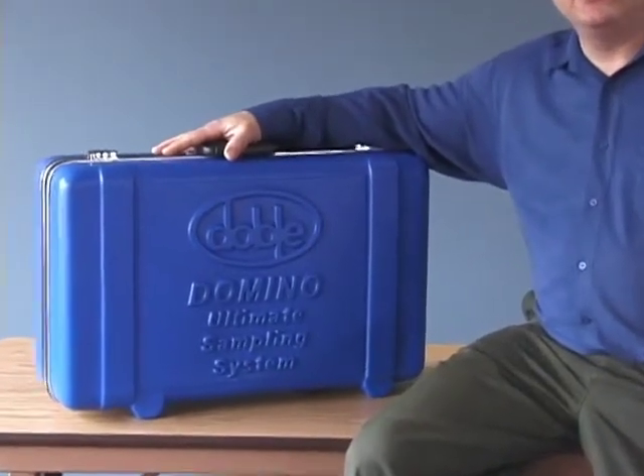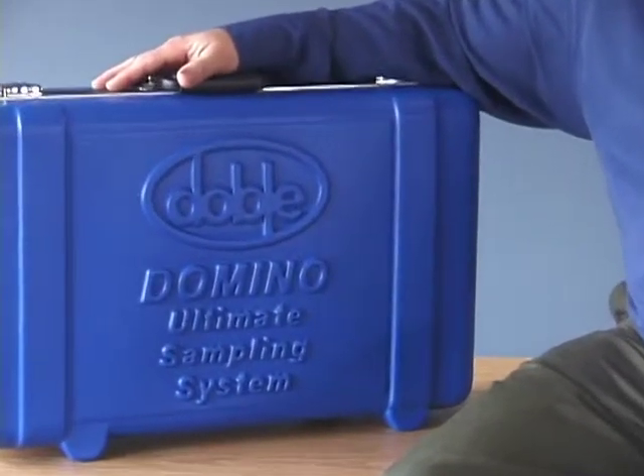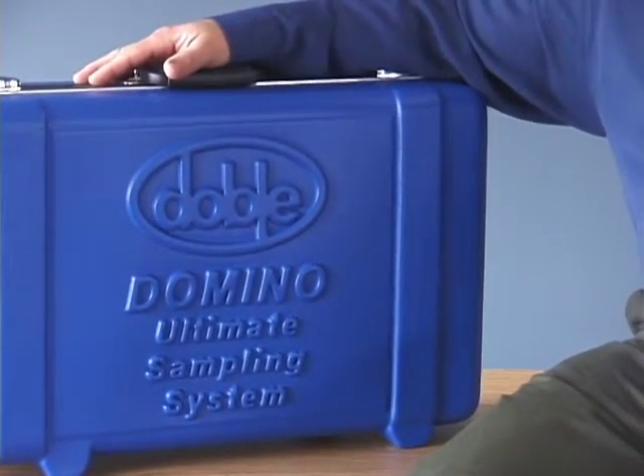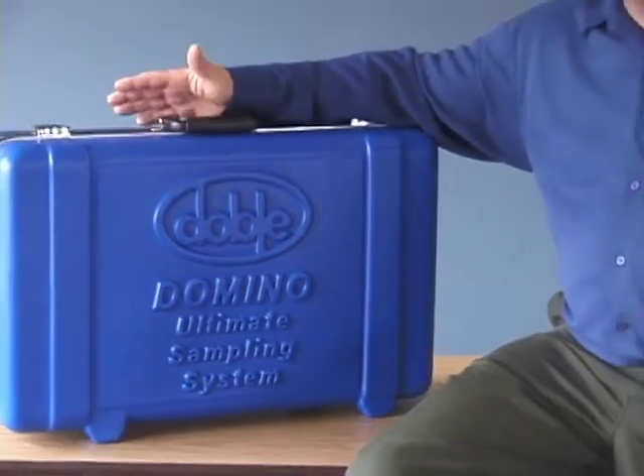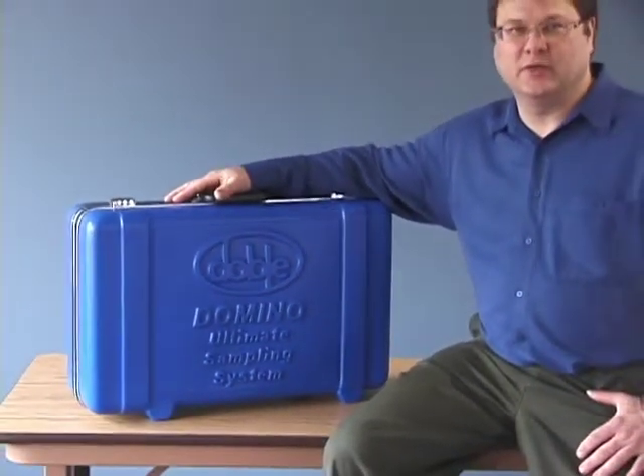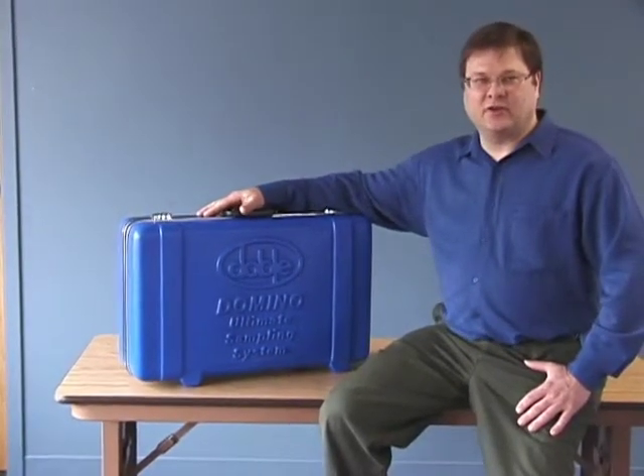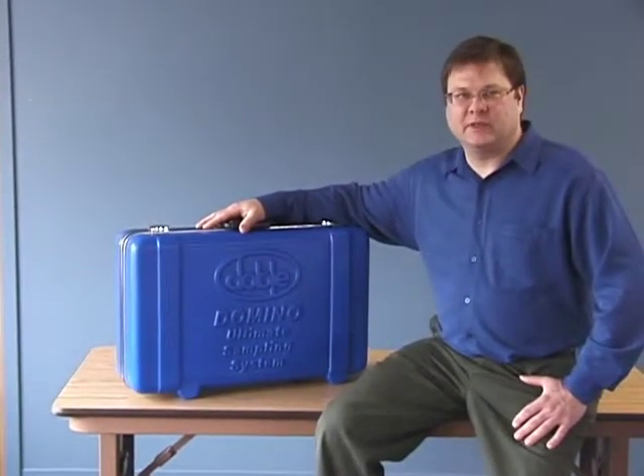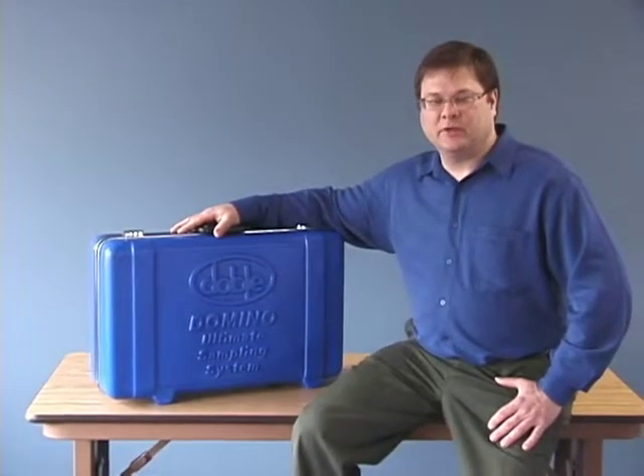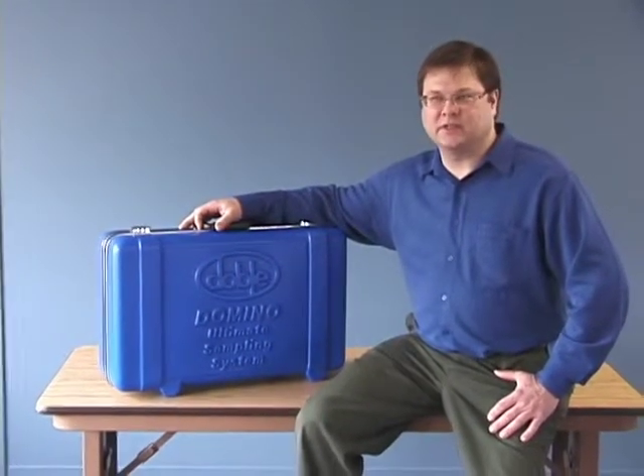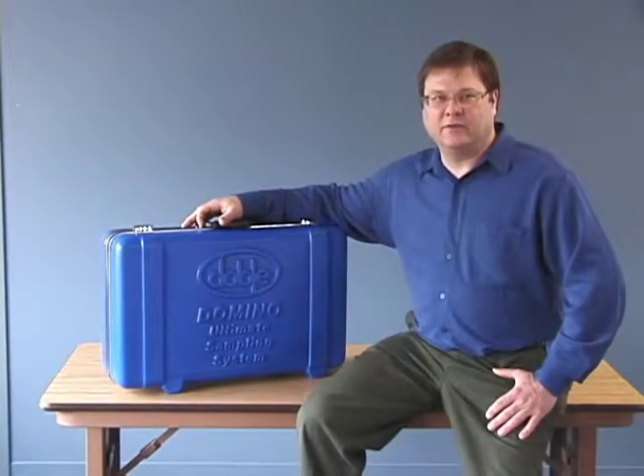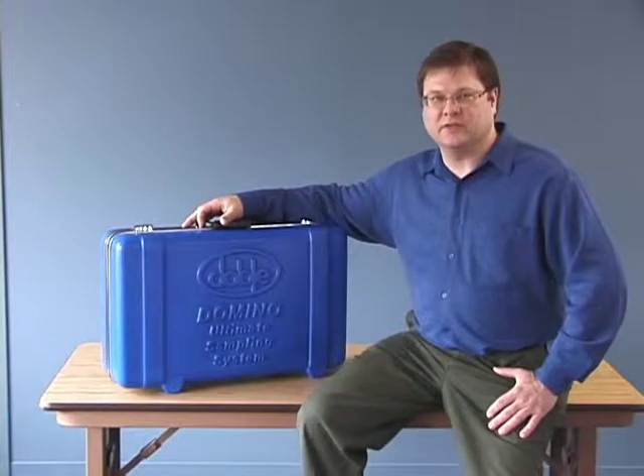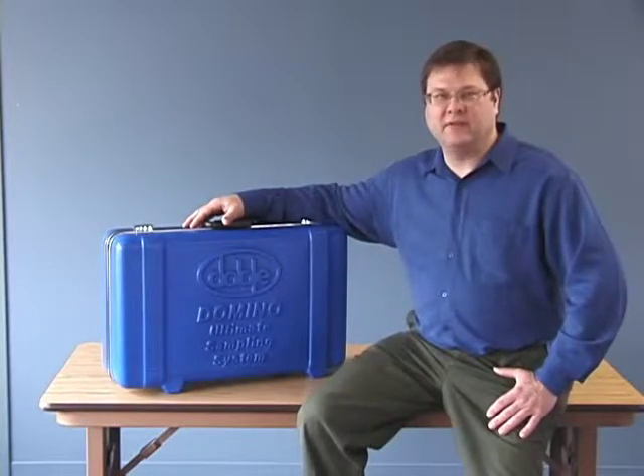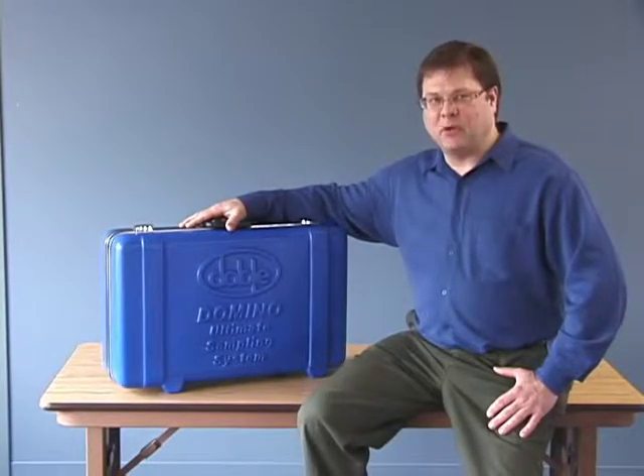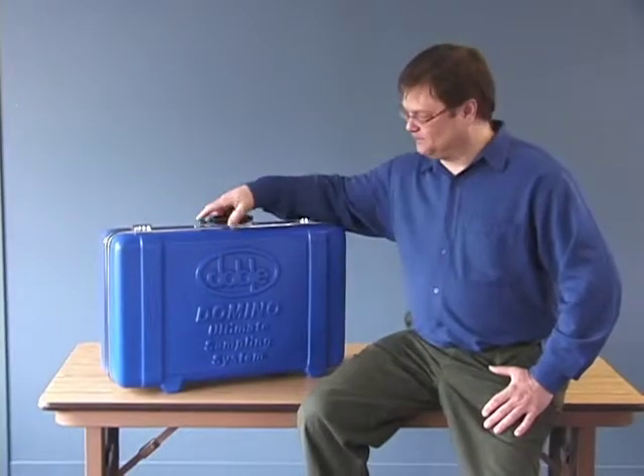This product will allow you to do a multitude of functions in the field, and it is truly a portable instrument. So let's talk first about what the Ultimate Sampling System, or USS, really is. It's actually a combination of tools to allow you to sample not only transformer mineral oils, but also other dielectric liquids as well, such as silicones, biofluids, also called natural esters, aged oils, and even things like the dew point of gases, or SF6. So let's take a look at the components and see what's available to you.